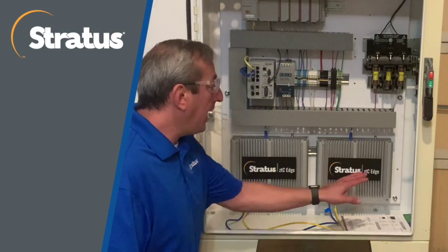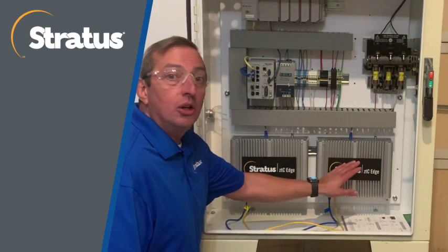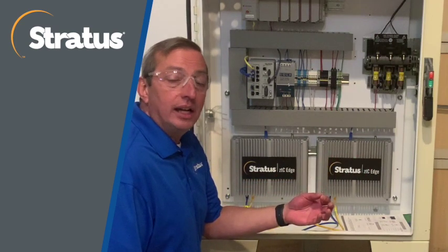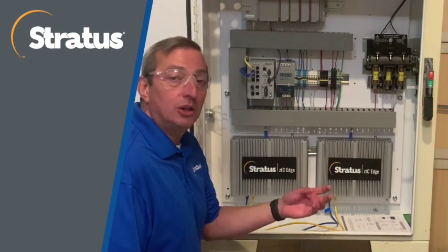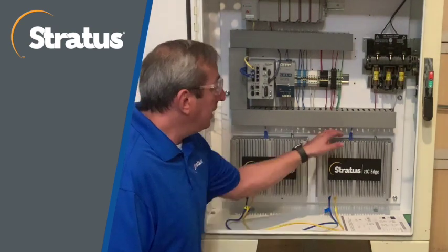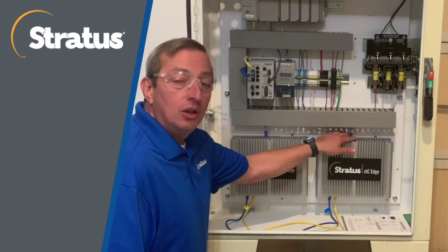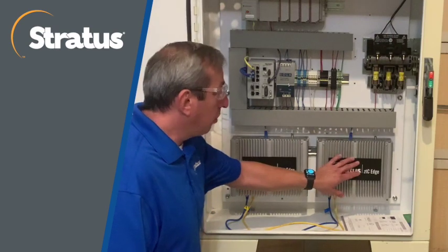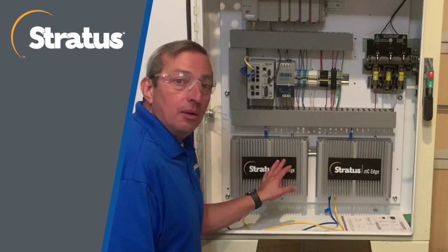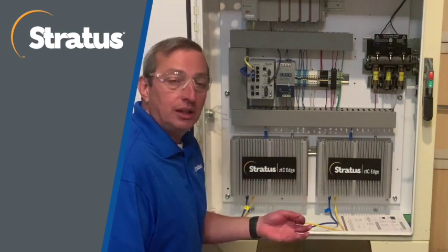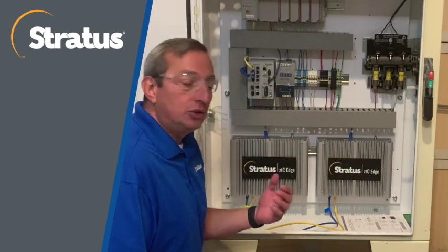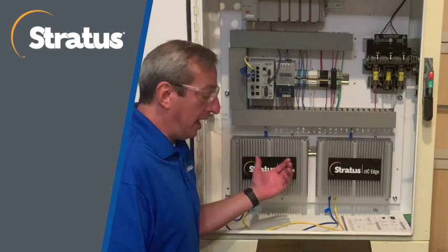So as you know, we had the Thin Manager image running on node 1 that was running the Thin Manager WinTMC client that we had multiple tiles up. We also had a remote desktop session running the HMI. And what I did is I actually pulled the network cable on node 1, and programmatically the image was migrated over to node 0. But the nice thing about it is, from an operator standpoint and from Thin Manager, there was never any interruption. So that truly shows the value of Stratus.